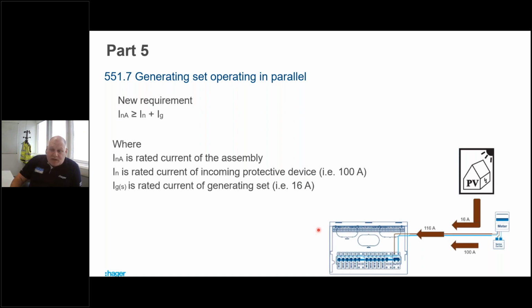There's a few ways around this. We can either put a limiting device in here, a double pole MCB instead of a main switch rated at 100 amps, so we limit the amount of current that goes through this board, or we can feed this 16 amps into the board in a different way. If we put that 16 amps into the end of the board through an MCB, we're not actually putting 116 amps through the main switch and the RCBOs and the RCDs.